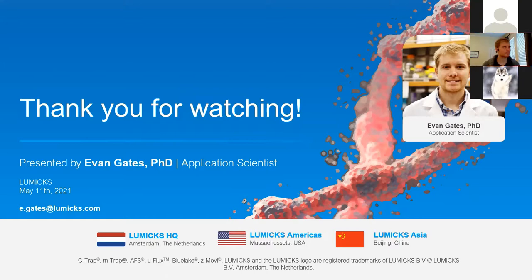Sure. Thank you. Yeah, I see one question. And Andrea, I wanted to ask you quickly. Will you be at, are you familiar with Woods Hole, their summer courses? Yes, I am. Oh, okay. Yeah, I don't know if you'll be going this year. But we're excited that they're finally opening it back up. And so we'll be there for a month this summer. But yeah, I would love to discuss with you how we could bring this potentially for a demo or something to get people hands on with the instrument. Excellent. And so going on to the question. Yeah. Can you tune the trap stiffness and can you program step or sinusoidal displacements? Yeah. Great question. Yes. So you can tune the intensity of the laser. You can tune the bead sizes you use and all of that can allow you to adjust trap stiffnesses. So if you're working with DNA, you might want a higher trap stiffness. If you're working with something like a motor protein, you probably want a lower trap stiffness.